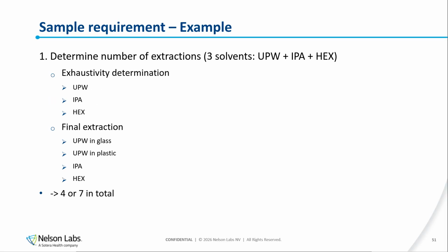So first, we will determine the number of extractions. And you will select a number of solvents. Later in the presentation, we will see which solvents you will select, but let's take this case of 3 solvents. Ultra pure water, which is water for injection, which is not sterilized, so very pure water. Isopropanol and hexane. So these are 3 solvents, but if, for example, you need to do an exhaustivity determination because you need exhaustive extractions, again, later we will see what this is, but you will need to do this for every solvent. And this is a separate extraction. So we already need 3 extractions.